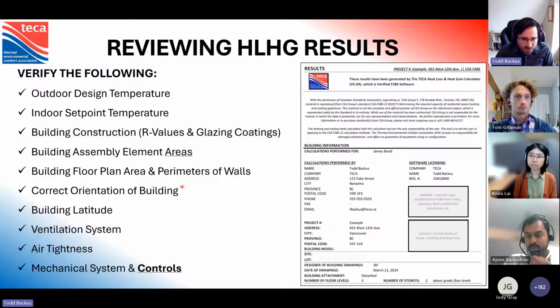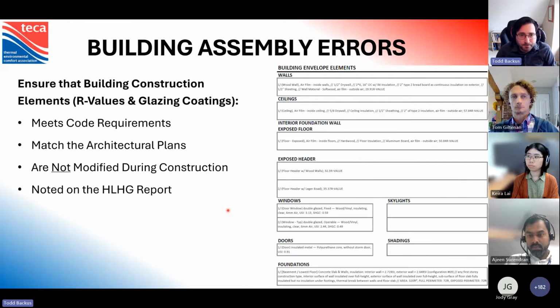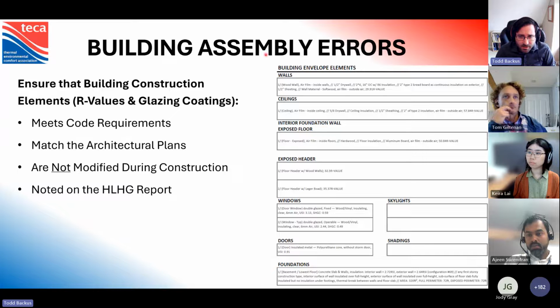The orientation, as I mentioned, is really critical. The building latitude, so make sure the location is correct. The ventilation system, air tightness, and the correct mechanical system and controls are selected. So looking at the building assembly, I've seen a lot of errors here. So just give it a double check, make sure that it actually meets your code requirements, that it matches your architectural plans, and that it's not modified during construction, because you don't want to do your model based on a home that's very well insulated only to have those R values reduced, because then your system's going to be undersized. The other thing to be mindful of is units.